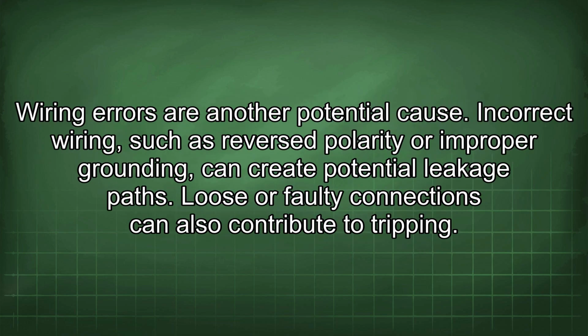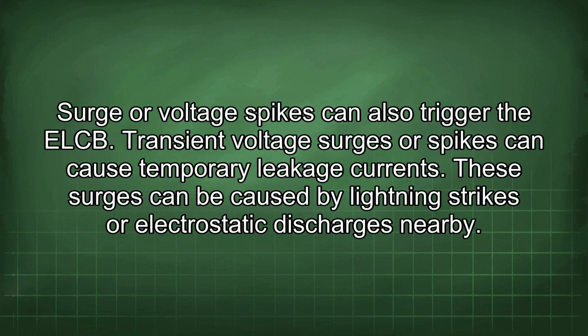Wiring errors are another potential cause. Incorrect wiring, such as reverse polarity or improper grounding, can create potential leakage paths. Loose or faulty connections can also contribute to tripping. Surges or voltage spikes can also trigger the ELCB. Transient voltage surges or spikes can cause temporary leakage currents. These surges can be caused by lightning strikes or electrostatic discharges nearby.